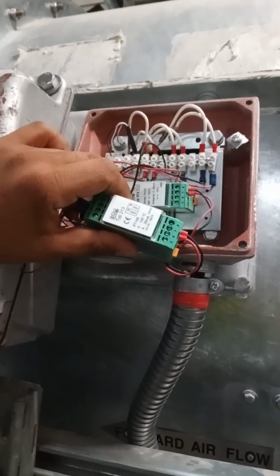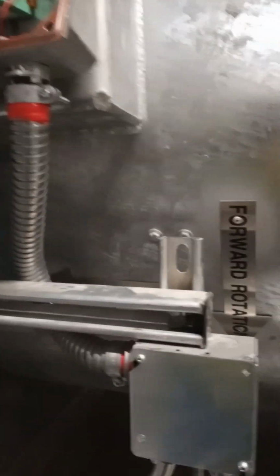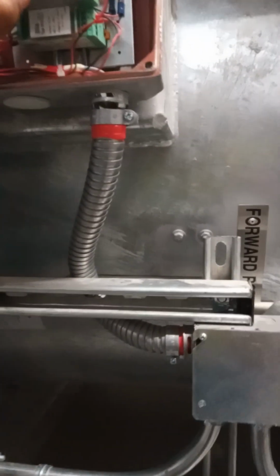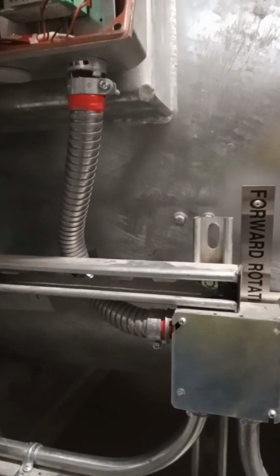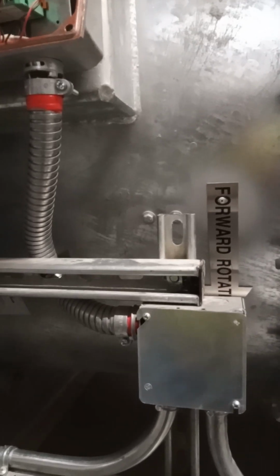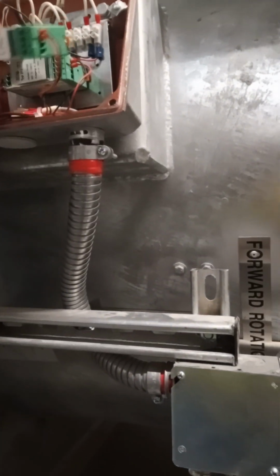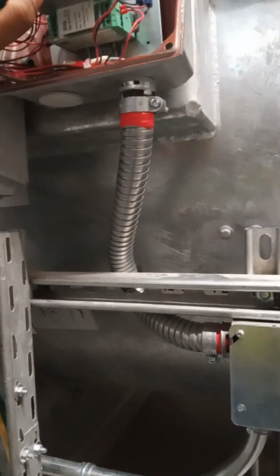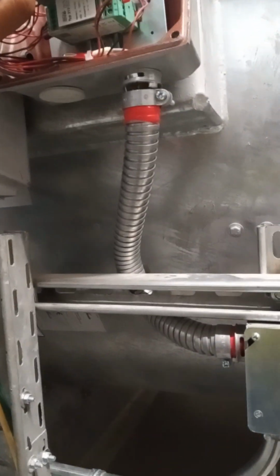Okay, and its channel settings. Channel settings shall be 4 to 20 milliamps, and the raw value high maximum is 32,767, and minimum shall be 11. That shall be the settings. And its calibration is 20 to 127 for temperature, and for vibration 0 to 50. That is the channel, and the raw value is 11 to 32,767 maximum.